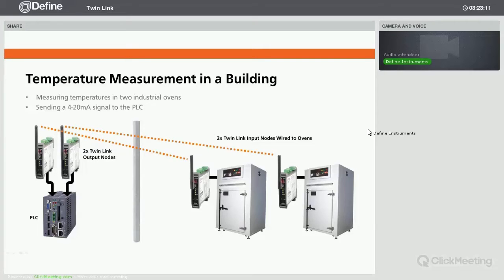2 RTD probes were connected to the TwinLink input nodes. The data was then transmitted to the output nodes in another area of the building, where the output nodes converted the signal to standard 4 to 20 milliamp PLC inputs. In this type of application, the TwinLink is specified to transmit up to 1,000 feet through walls and obstructions. Remember that this distance can be increased by using our repeater units. What the customer loved about this application is that they did not need to lay any additional cabling, and commissioning took less than 1 hour.